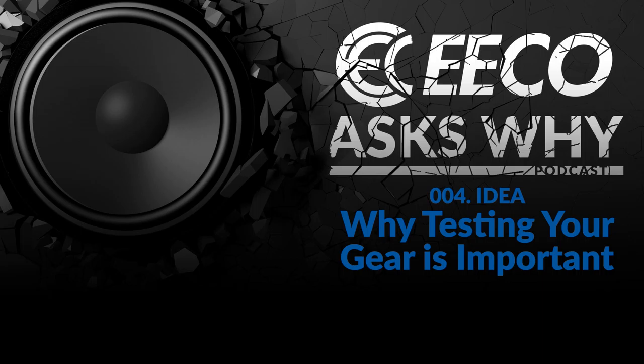Absolutely. So before we start testing and we get into that, we probably should have some basic information in place, right? So can you walk through some of these items of typical information that users should have available before they actually begin testing? I'm thinking through items like short circuit studies, coordination studies, arc flash analysis, load flow studies, and a general harmonic analysis. If you could walk us through those to give a high level overview of what they are and why they're important, that'd be a great place to start.